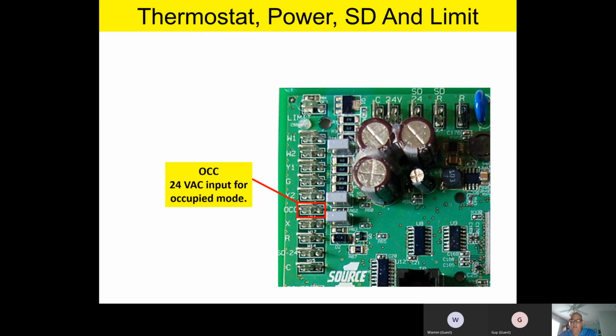And then what that'll do is ensure that you, and by the way, this board will handle up to 35 volts, up to 35 volt low voltage without any problem at all, I've been told, even though the nominal voltage is 24. So double check your connection, make sure there's no loose connection on that jumper wire between SD24 and SDR. Low voltage and grounding are the top things I'd ask you to check if you're having issues with that intermittent SD24 and SDR fault. Excellent question. Any other good questions?